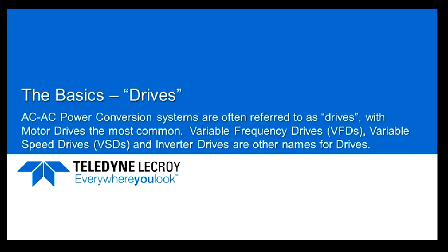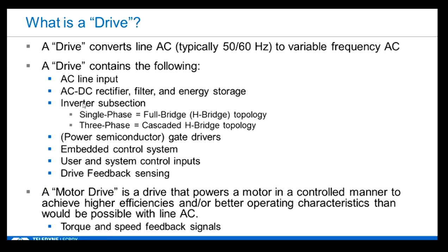Okay, so now let's talk about a drive. This is where everything comes together. The inverter subsection, that power conversion section, is one part of a drive. So what is a drive? A drive is really something that converts line AC, typically 50 or 60 hertz, or it could work directly from a battery as well, to a variable frequency AC output.